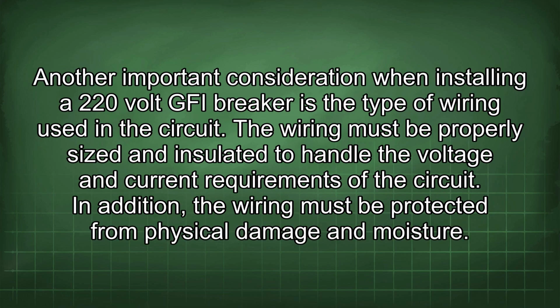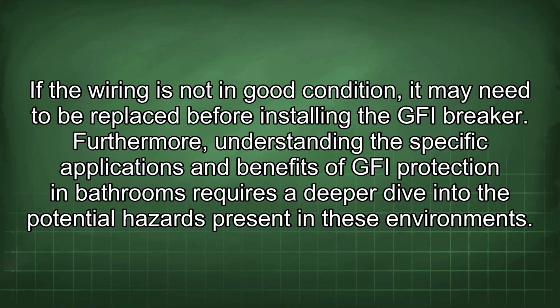Another important consideration when installing a 220-volt GFI breaker is the type of wiring used in the circuit. The wiring must be properly sized and insulated to handle the voltage and current requirements of the circuit. In addition, the wiring must be protected from physical damage and moisture. If the wiring is not in good condition, it may need to be replaced before installing the GFI breaker.